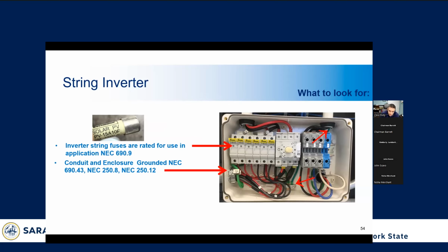More on string inverters. Here we're taking a look at the conduit bonding that is crucial to a safe installation. You can see this is a non-metallic enclosure, and the conduit coming in and out over here and over here are metallic, so you have to make sure that the ground path from here to here is continuous. You can see there's a ground lug installed in here, and these little clamps allow that ground path to continue from this conduit to this conduit.